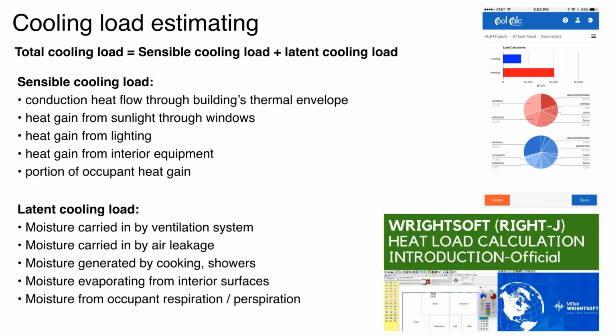And for estimating these loads, one of the most commonly accepted methods today is what's called Manual J. And typically today it's done with software. I just put a couple examples up there. There's CoolCalc that is based on Manual J. You can Google that and get some information on it. Right-Suite, Right-J has been around for years. It's been expanded over the years to the point where you can actually draw the building and it will automatically scale out walls and windows and so forth for you. And again, you're going to have to put in data such as wall area, window area, and so forth, but also orientation. And the program is going to calculate things like solar heat gain through windows. That's a starting point. You have to identify or estimate what that load is before you start selecting equipment.